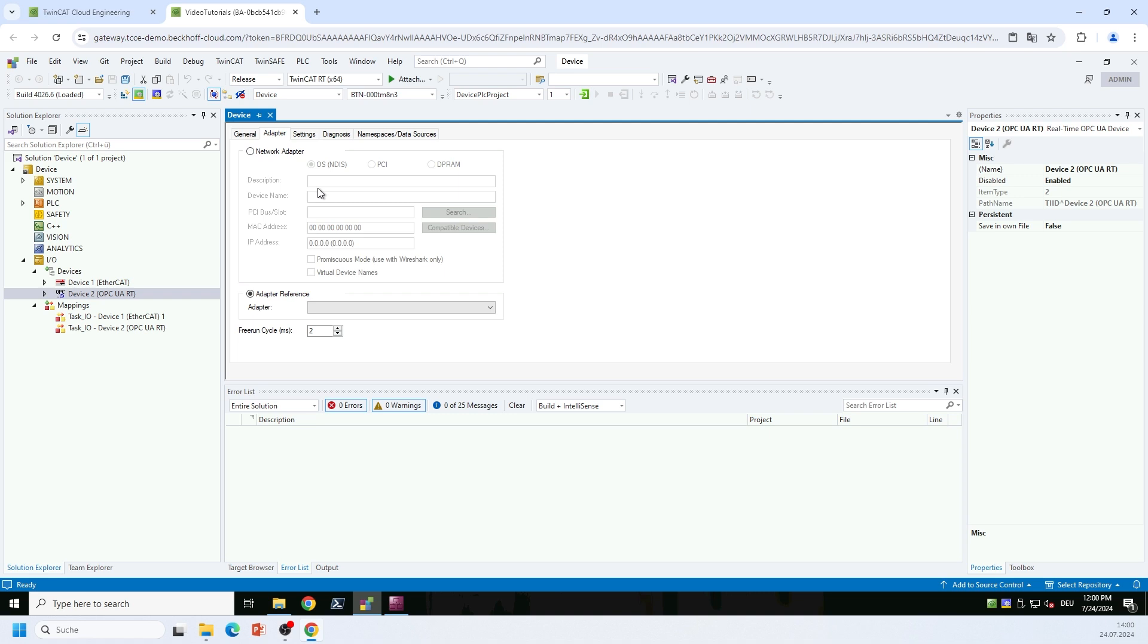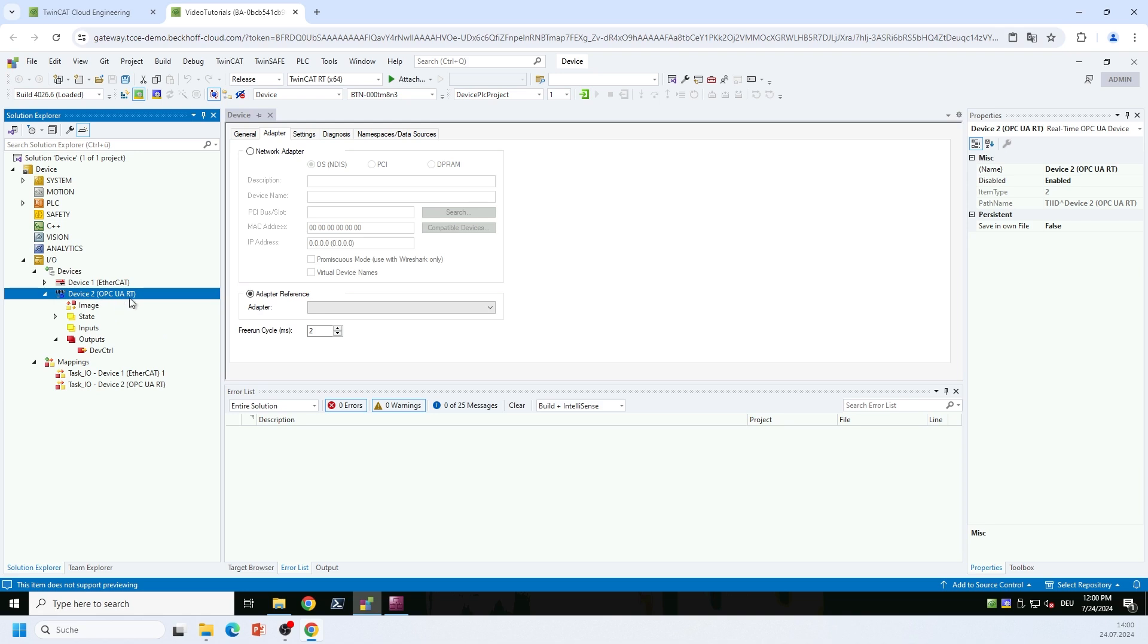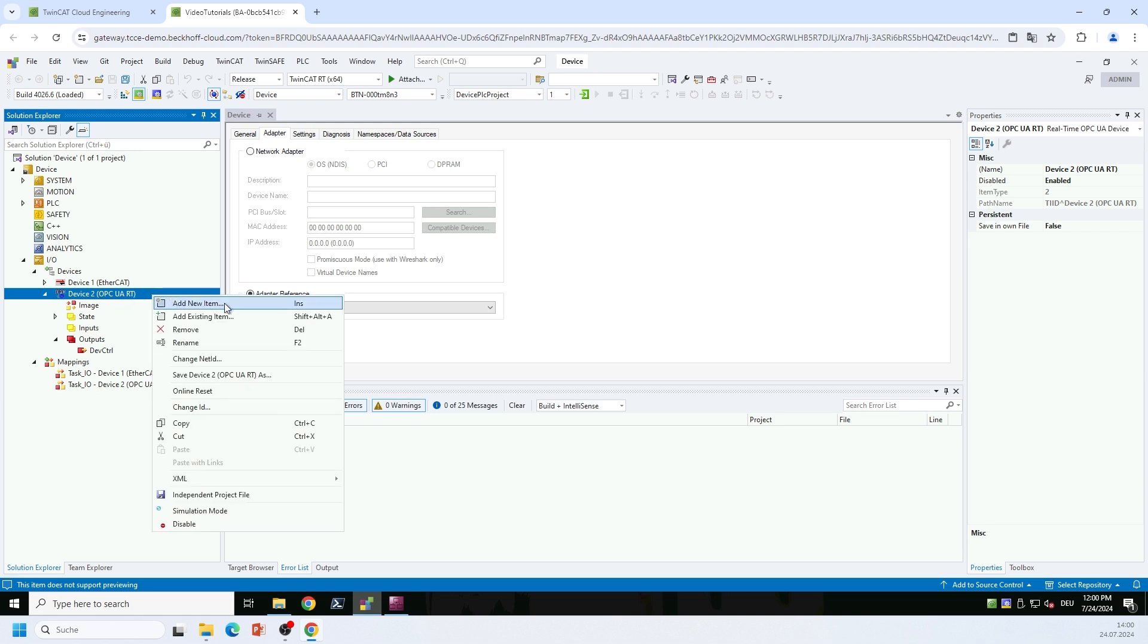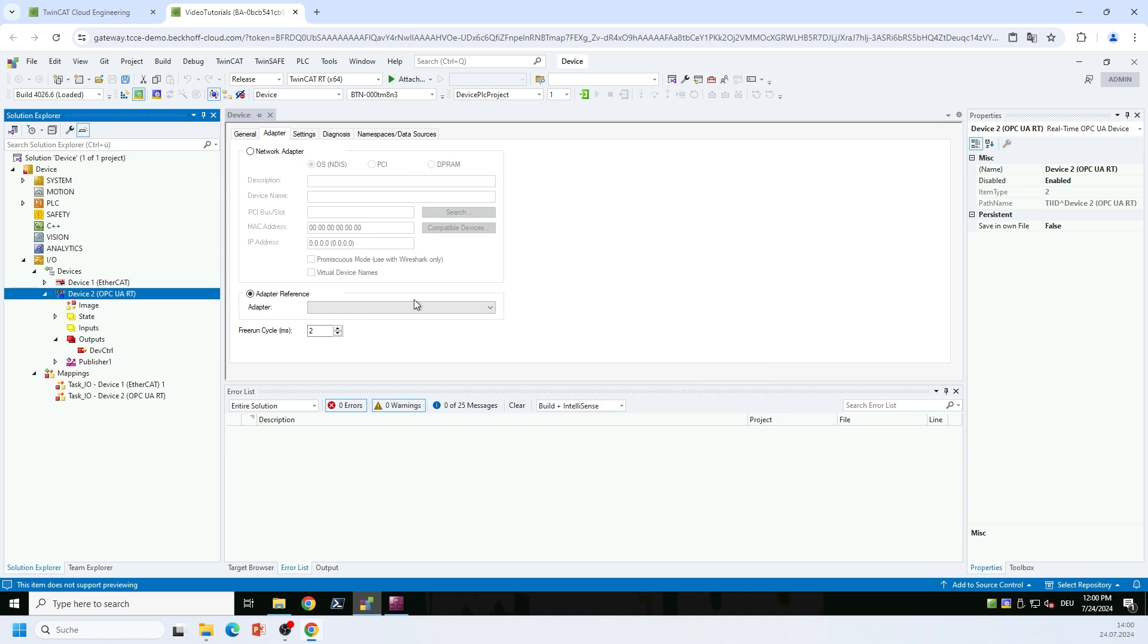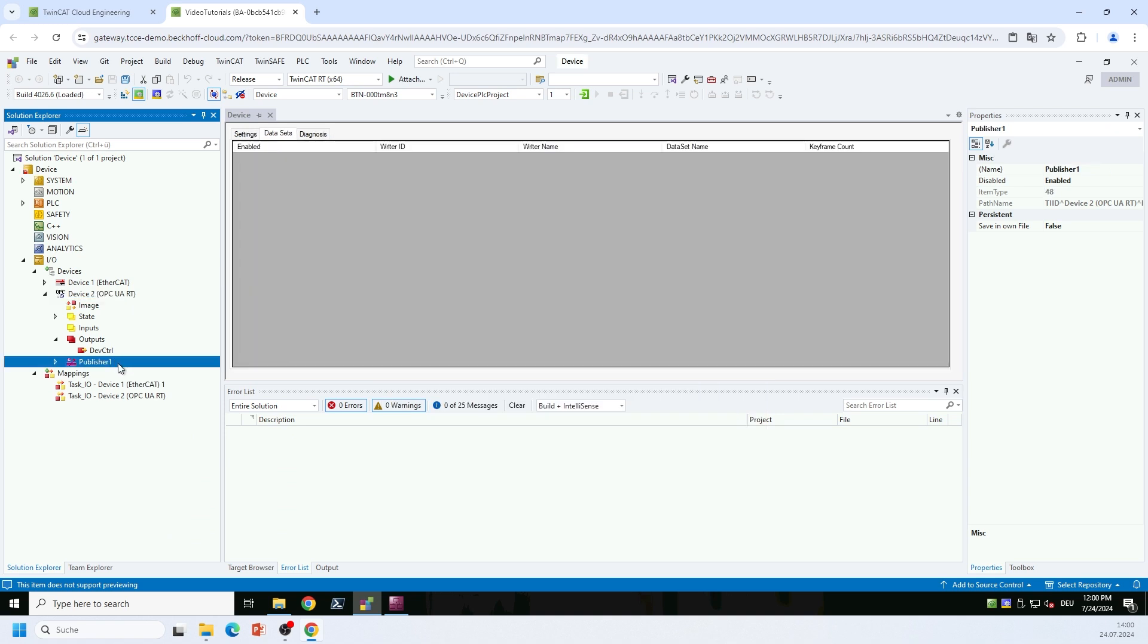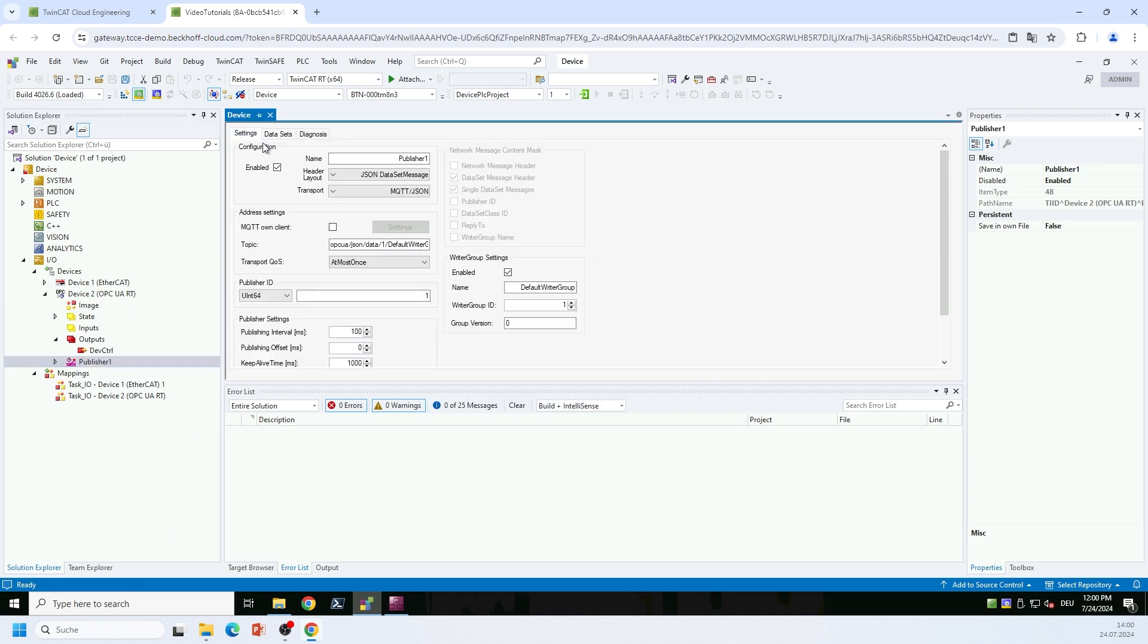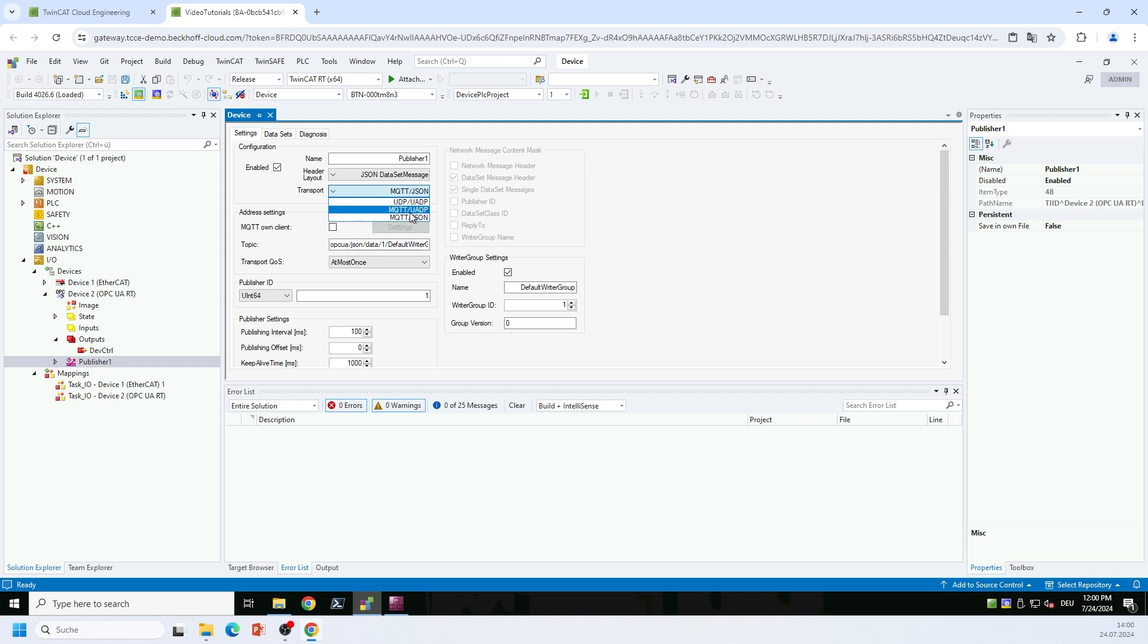So we now want to configure a publisher on this OPC UA RT device, so we right-click the device and we select add new item. In this dialog here I can select the OPC UA Publisher module. So I add this module to my configuration, and on the publisher node you can specify different settings. Of course you can specify the transport that you would like to use. In our case we want to use MQTT JSON, but we can also use MQTT UADP, which is a binary data format which is more efficient than the JSON, but in our example here we want to stay with the JSON format. You can also specify a topic on the message broker that you would like to publish the data to, specify quality of service settings, and many more settings that I don't want to dive into right now because time is short for this video tutorial.